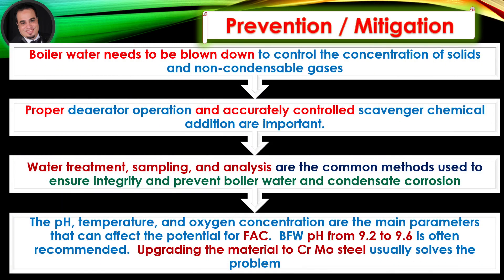Prevention and mitigation. Boiler water needs to be blown down to control the concentration of solids and non-condensable gases. Proper de-aerator operation and accurately controlled scavenger chemical addition are important.